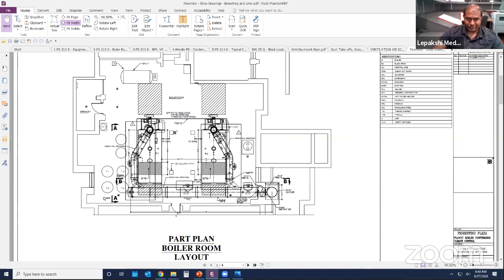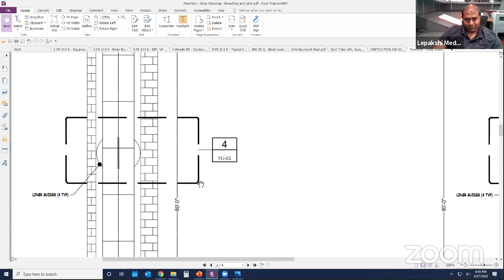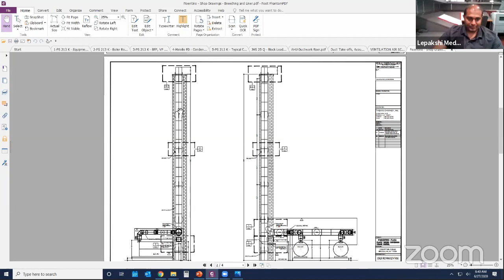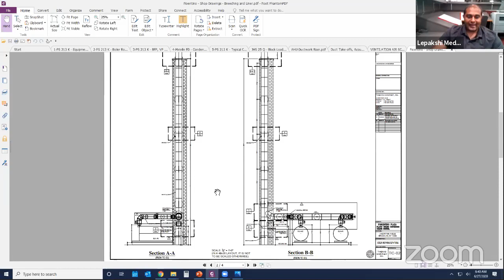First, this chimney in this particular example—this is the project we're currently dealing with—the chimney height is probably about 80 feet. So the chimney is 80 feet high, exhausting flue gases from this boiler out to the atmosphere. You have to calculate the available draft from this chimney height.